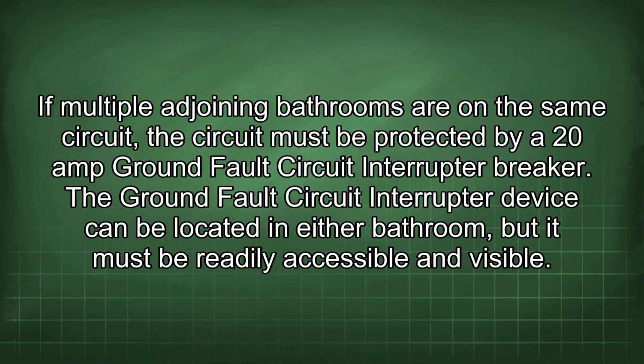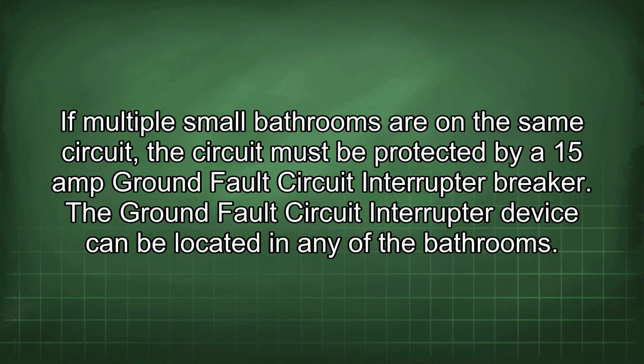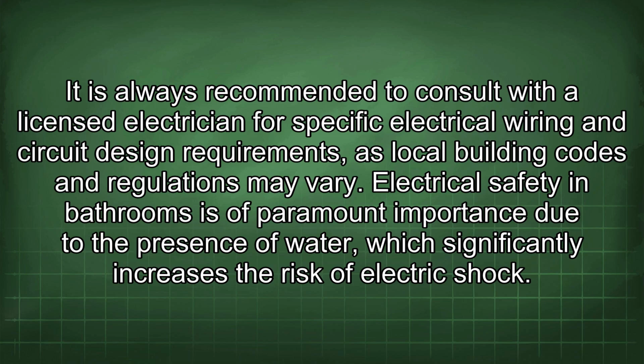The ground fault circuit interrupter device can be located in either bathroom, but it must be readily accessible and visible. If multiple small bathrooms are on the same circuit, the circuit must be protected by a 15-amp ground fault circuit interrupter breaker. The ground fault circuit interrupter device can be located in any of the bathrooms. It is always recommended to consult with a licensed electrician for specific electrical wiring and circuit design requirements, as local building codes and regulations may vary.